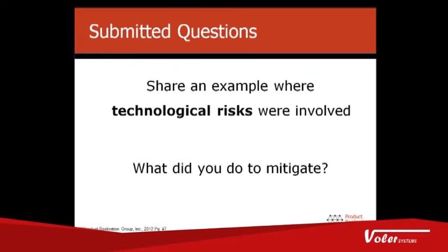A good example of a risk that we dealt with recently was on a device that monitors an AED, which is a defibrillator, the ones you find in airports. The challenge we had was that it has a self-check and it reports on a screen what its state is, and we needed to read that and report it. It seemed straightforward. You have a photo detector. It was simple. We could just see if it was dark or light, and we provided illumination with an LED.